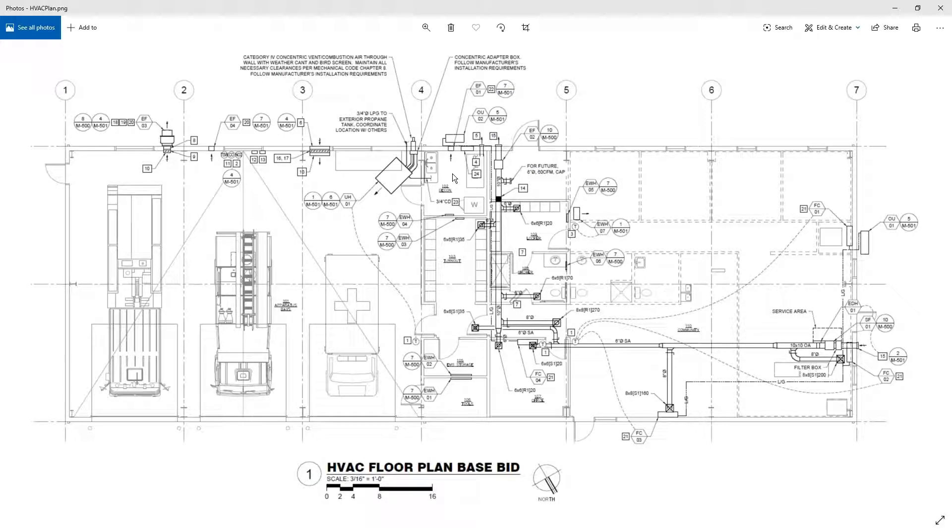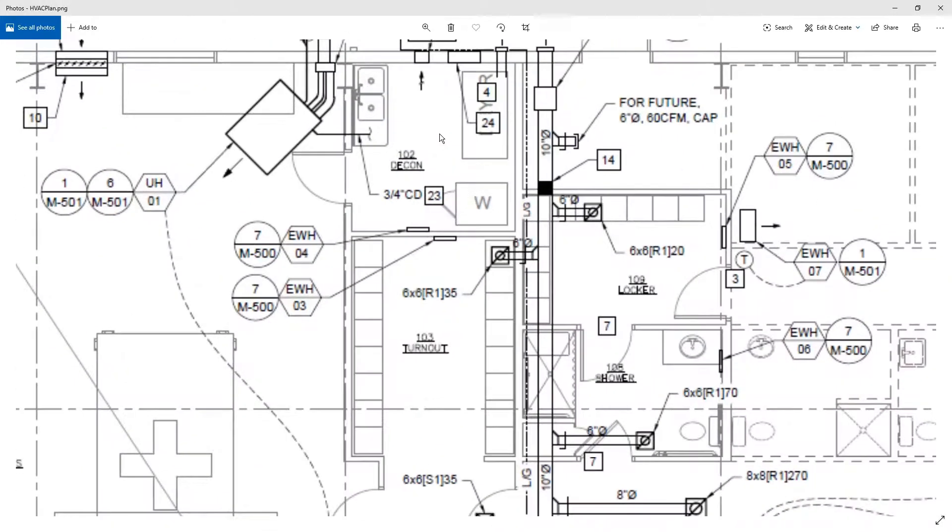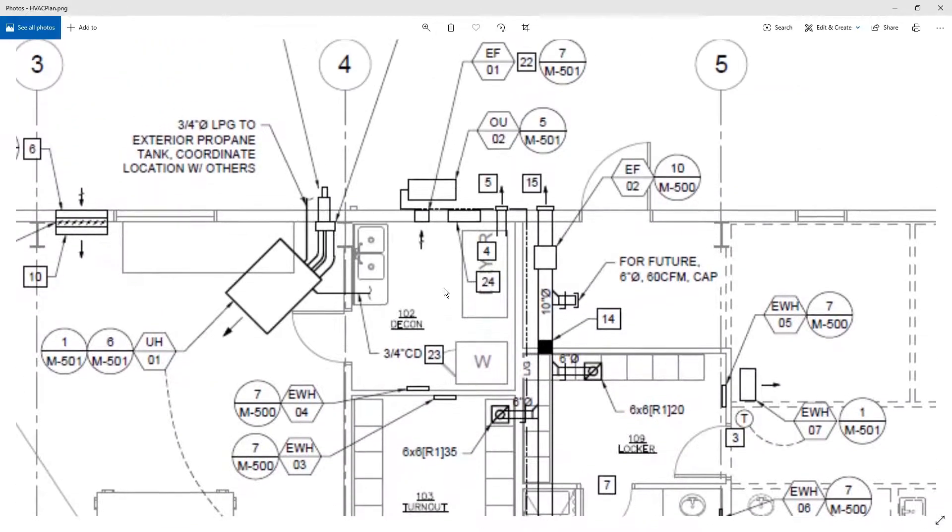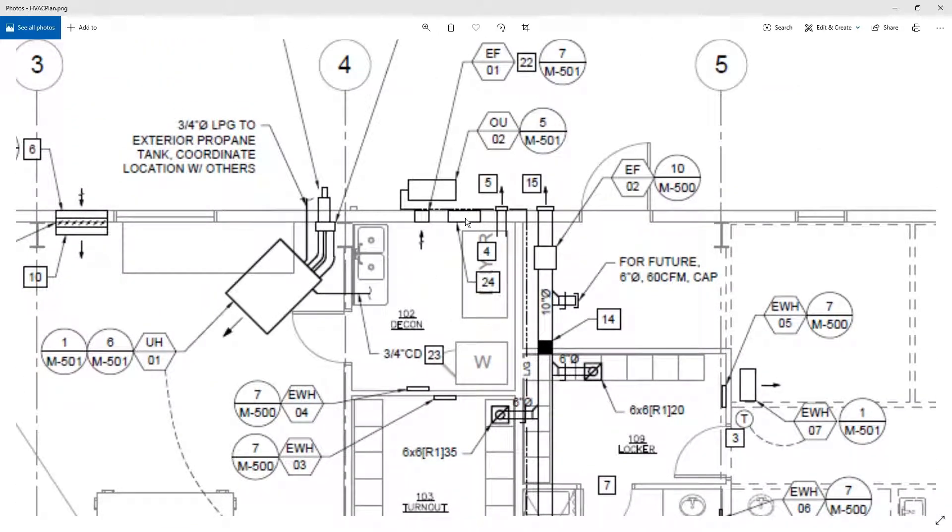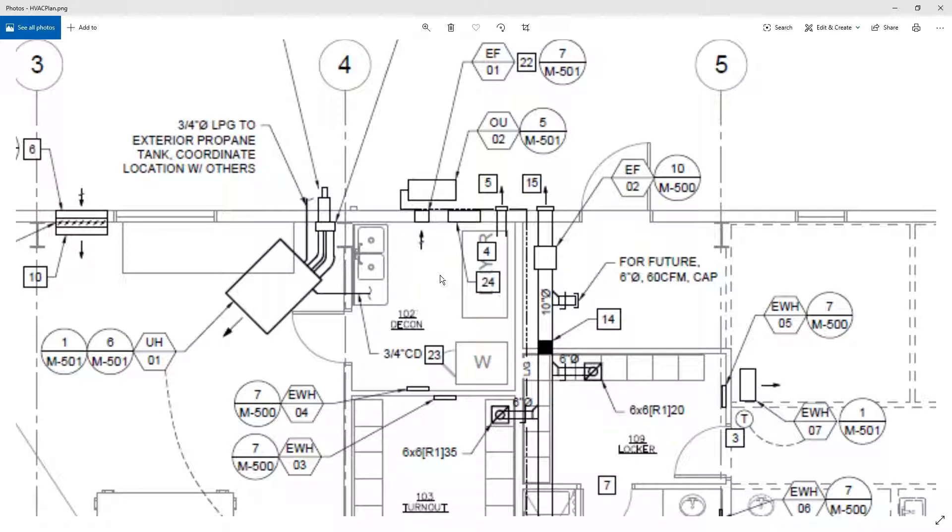For this decontamination laundry room, we actually have an exhaust fan and a makeup air louver in the wall. We have the exhaust fan operating, but we do not have any way for the energy model to know where to get makeup air. The exhaust fan is probably just exhausting any infiltration to the room.